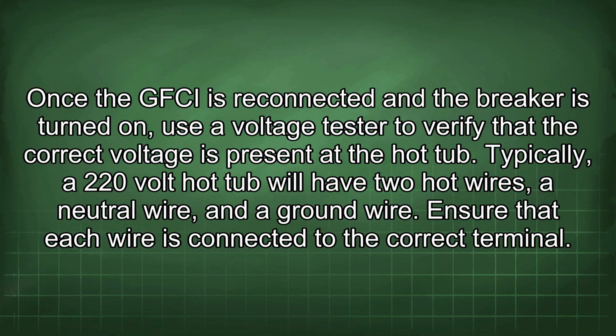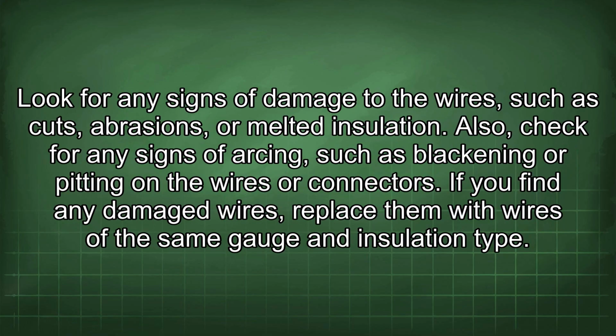Ensure that each wire is connected to the correct terminal. Look for any signs of damage to the wires, such as cuts, abrasions, or melted insulation. Also, check for any signs of arcing, such as blackening or pitting on the wires or connectors. If you find any damaged wires, replace them with wires of the same gauge and insulation type.